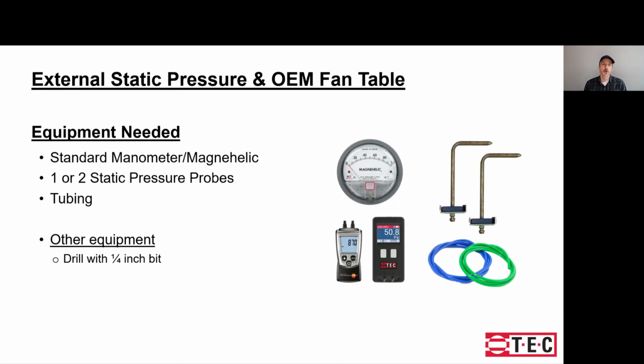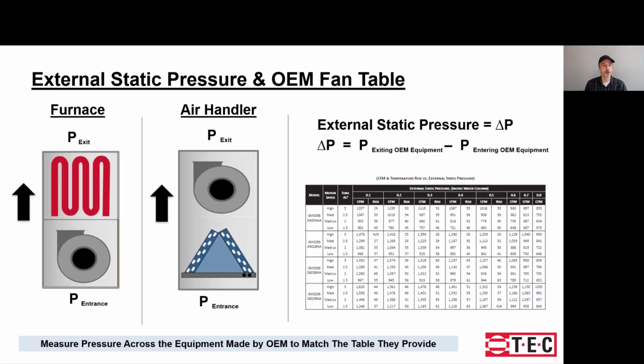Okay, so for equipment on this method, what you're going to need is a digital manometer or a magnehelic gauge. The magnehelic has the benefit of no battery. The digital manometers will be more accurate. You'll also need a static pressure probe and the tubing, and then you're going to need a drill to drill the holes.